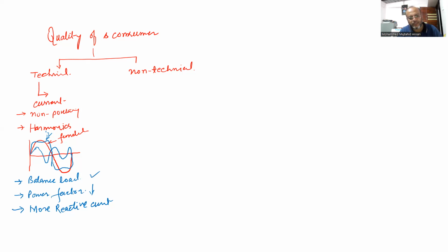Large number of single phase loads are there. Even though there is a large number of single phase loads, the connected load is not distributed well, and hence it is producing unbalanced current and unbalanced voltage. Power factor is poor, and more reactive current is drawn by the single phase loads, or say some induction machines. So this is the technical part of the consumer, and because of this technical part, the consumer also makes some pollution in the power system, and equally shares responsibility for bad quality of power supply, isn't it?